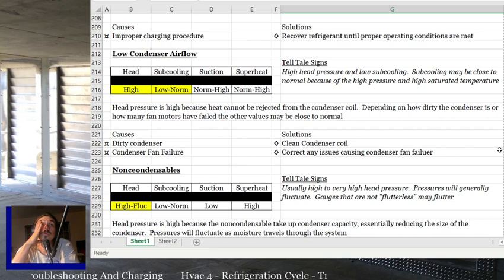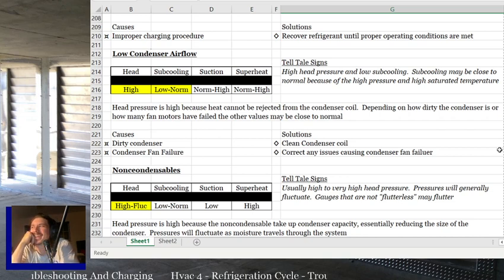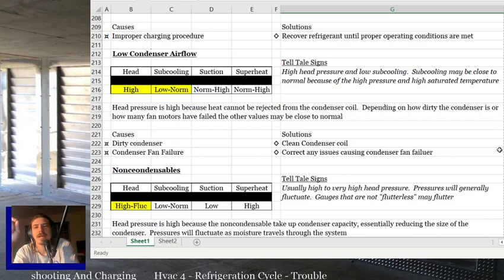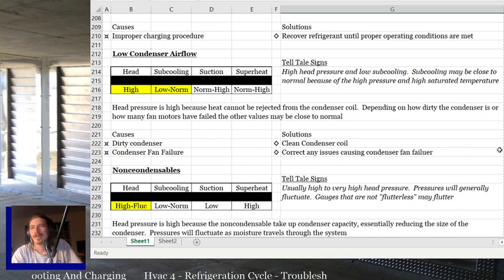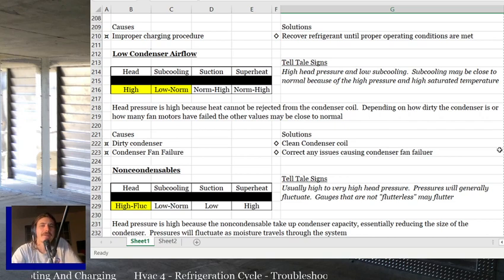I actually read an article probably a few weeks ago where some engineer or something actually said you don't really need to clean your condensers. And I'm not kidding, man. I'll have to see if I can find this article. It's just an article on some random website, right? But still, who writes this? His reasoning, of course, was that the system still functions pretty well, even if the condenser's dirty. Well, yeah, it does, bud, but you're using like 20-30% more energy than you need to. That's the point. Your head pressure's high, and you're basically making the compressor work harder than it should have to. It doesn't matter that it functions fine.